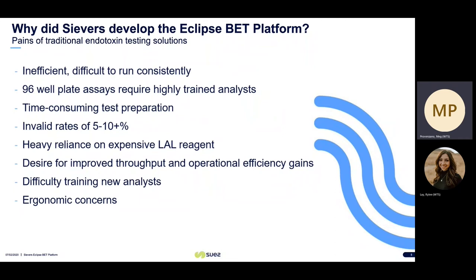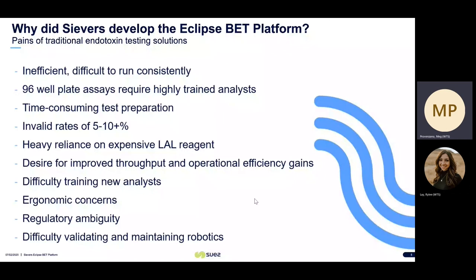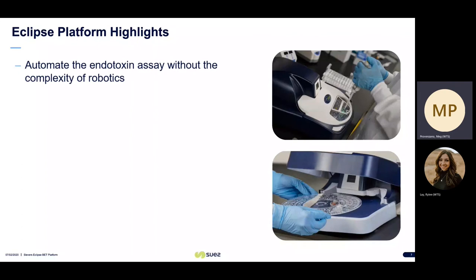There can be some difficulty in training new analysts — it can take a month or two to become proficient at running the bacterial endotoxin test. Ergonomic concerns are another reason why we developed this; with traditional methods, there are hundreds of pipetting steps per assay, which can be greatly reduced using the Eclipse platform. There could be some regulatory ambiguity in some circumstances, and with robotics, it can be difficult to validate them and maintain the instrument itself.